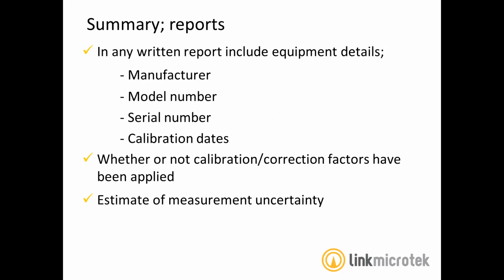So, in terms of reports then, in any written report, make sure you include the equipment details. So the manufacturer, the model number, serial number, calibration dates, whether or not calibration correction factors have been applied, and an estimate of measurement uncertainty.